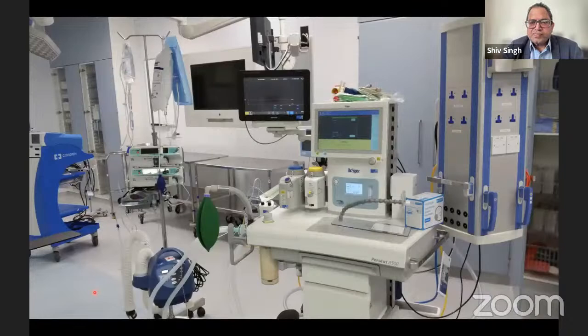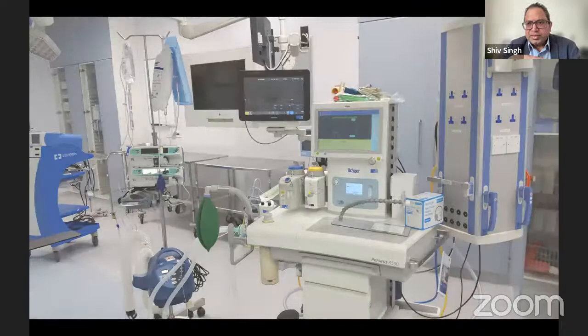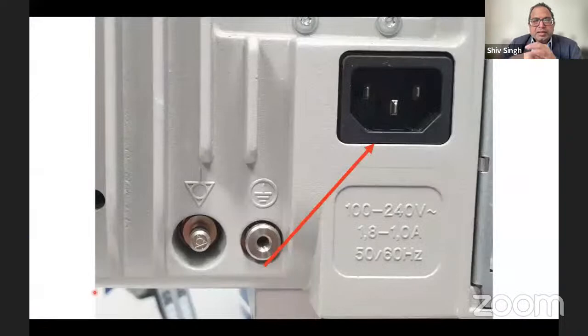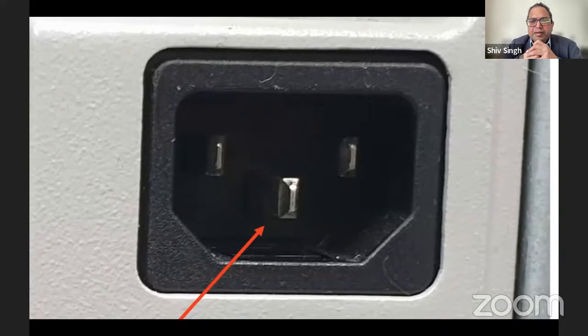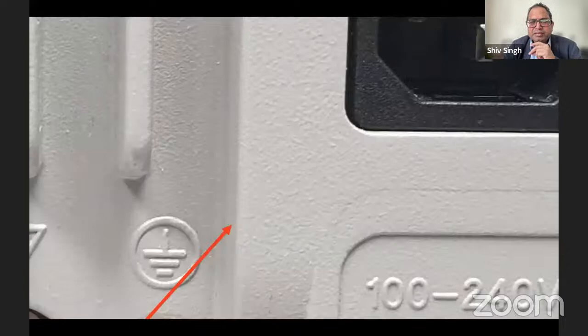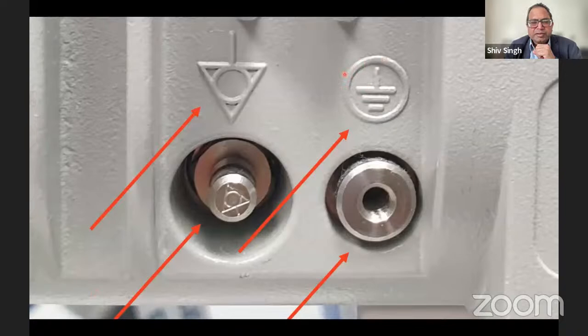We talked about this, okay? So if you look at it, that's the power source. That's the earth. That's the functional earth. And you see these points. You see a point on the right side, that one. And you see this symbol, which is the earth in a circle, that is your protective earth. And there's another point, which is like a peg, and this is a circle inside an inverted triangle. And that's an equipotential point. So these are all there on the machines.